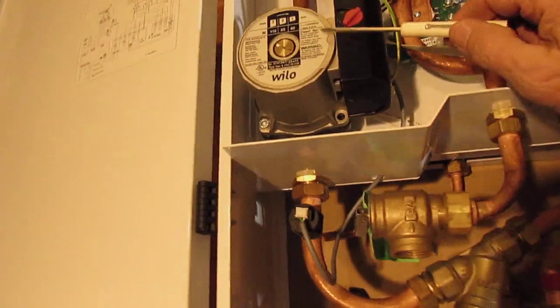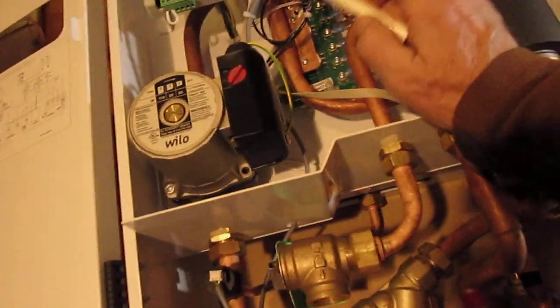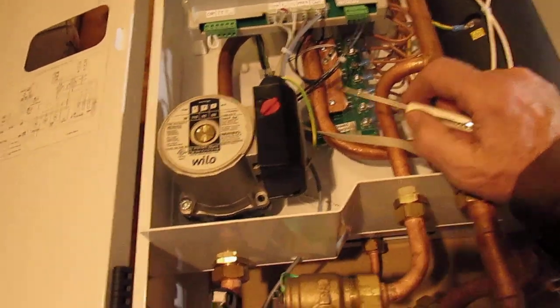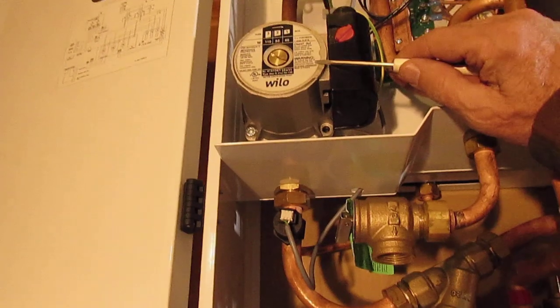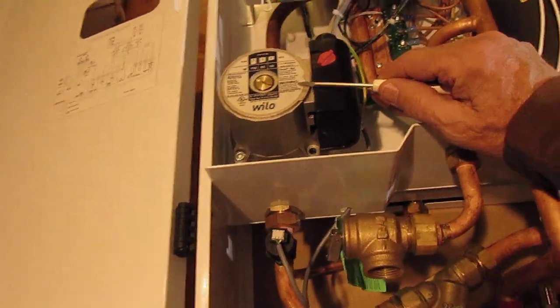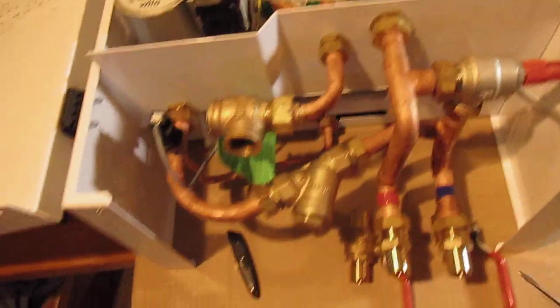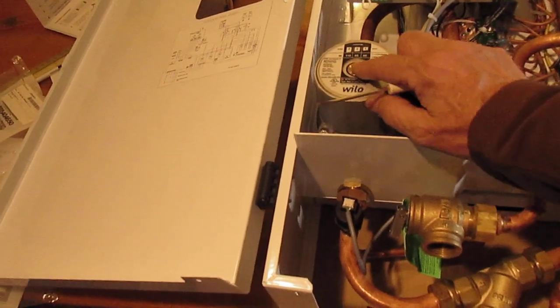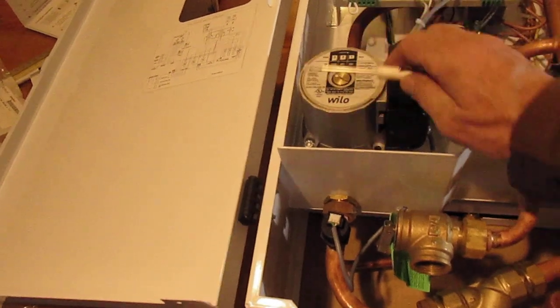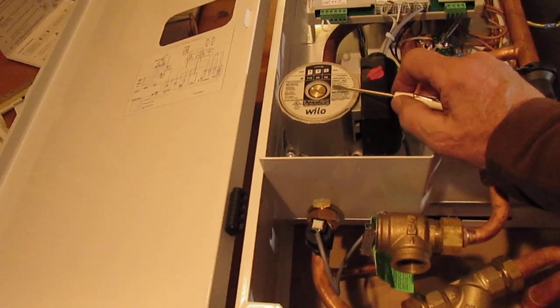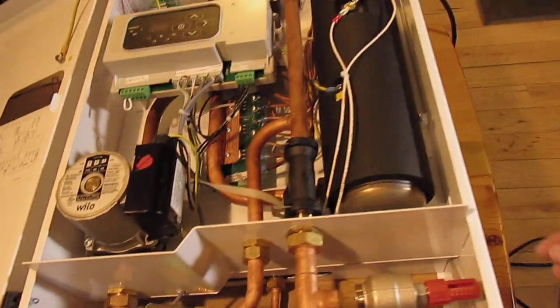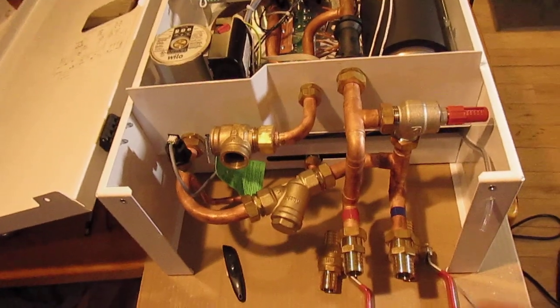Now these pumps come, they must test it for pressure or test it for leaks, right. And I think these things are made in France. I'm not really sure, but when you're shipping them in the winter time, it's like cold out. Like right now it's 11 degrees Fahrenheit. And so we actually froze up a pump. We couldn't figure out why the pump wasn't turning. So we kind of did some work on it and figured out it was really cold. It was frozen because it's sitting in the shop with no heat. So on the side of the box, it'll say zero to 50 C. That means don't freeze the thing, but they're shipping it in cold weather. So hopefully nothing's broken.